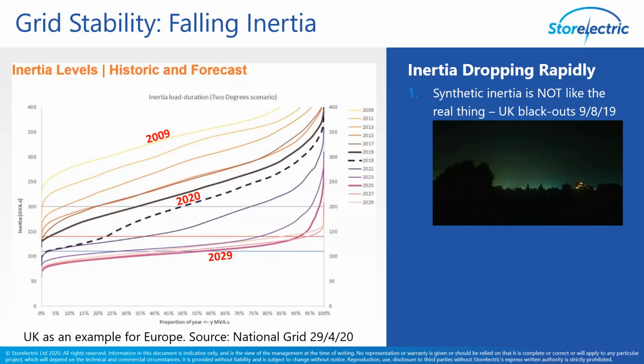And that's the result in Britain last August the 9th of not having real inertia. They had lots of synthetic inertia from batteries, but because batteries have to be triggered, that gives a response time. Because of the response time, whether it's milliseconds or seconds, the rate of change of frequency is still very, very high. The delay between the failure and the response time is a spike in the electricity system, and that's what caused the problem. So only real inertia can prevent it happening. On the other hand, synthetic inertia was very good for helping it to recover from the problem.